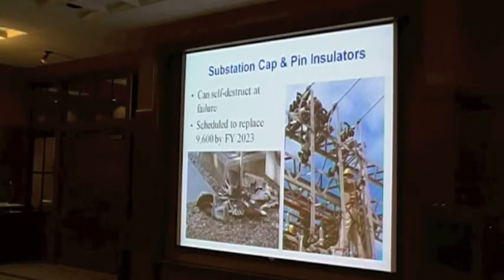But with the 69 kV, you can see he's actually standing on one of the structures right there. These are the older components, probably 50 to 60 years old—older technology. Gabe brought us a sample of the newer technology, and you can see that, yes, it's still a stress member, but the insulating porcelain component is one unit versus these being separate units. There are some advantages to the newer technology.